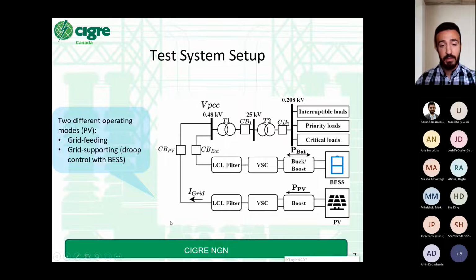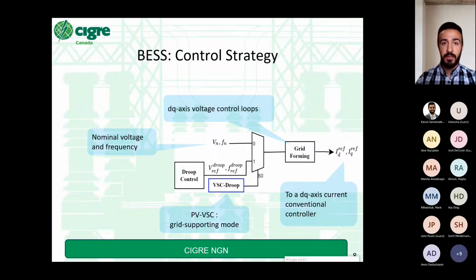A VSC that has two different operating modes, a grid feeding and a grid supporting, in which for a grid supporting, a droop mode is going to be applied in order to form the grid along with the battery energy storage system. This is the battery energy storage system control strategy. If the PV VSC is operating in a grid supporting mode, then there is a droop control that will generate the V reference and the frequency reference for the D and the Q axis outer voltage control loops. Whereas if we are operating in a grid feeding control, we will operate at the nominal voltage and the frequency.